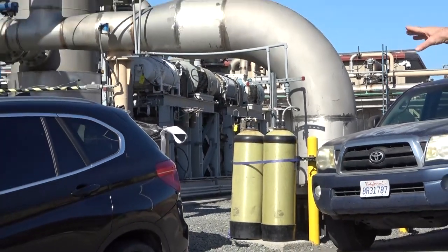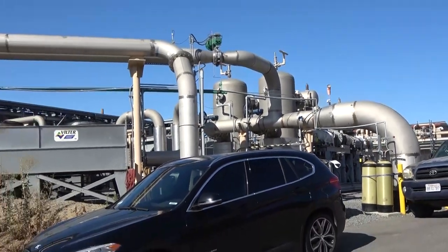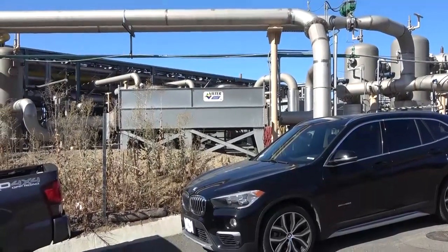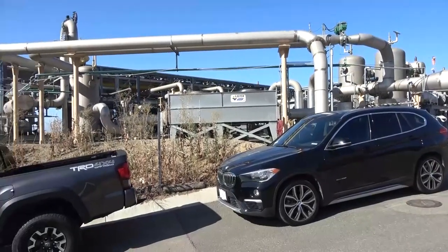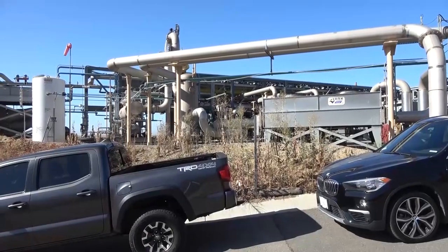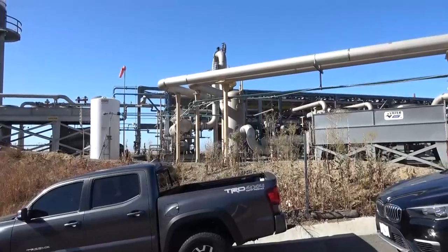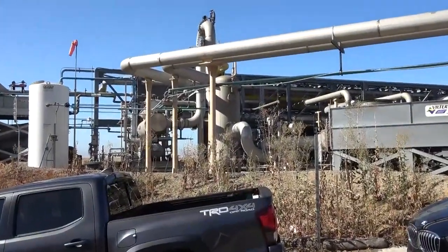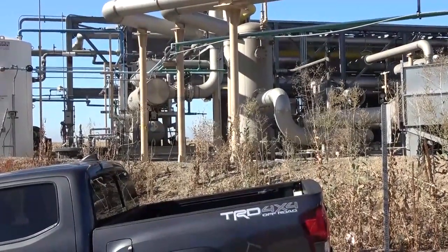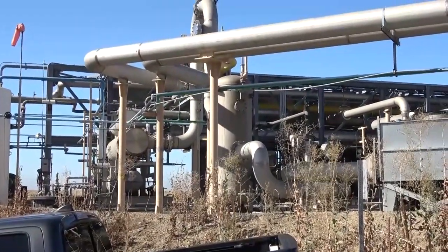The compressed gas drops below, and as we swing to the left, you can see this big device labeled 'Vilter' — that's actually a large air cooler, which lowers the temperature. To the left of that is another scrubber that removes more particulate matter and condensate. Immediately behind that is a chiller, which cools the landfill gas even more, so any liquids that come out as the temperature drops are collected and drawn off.